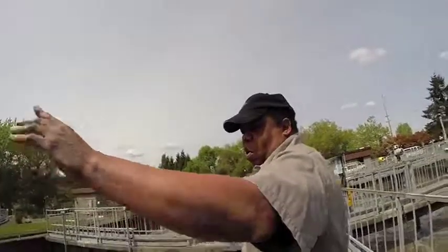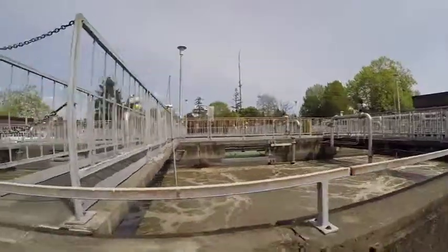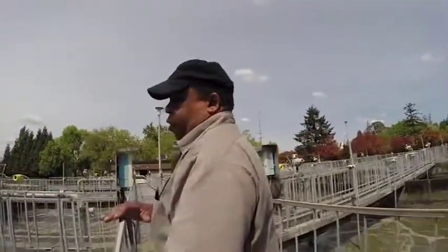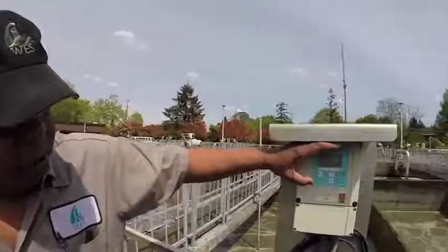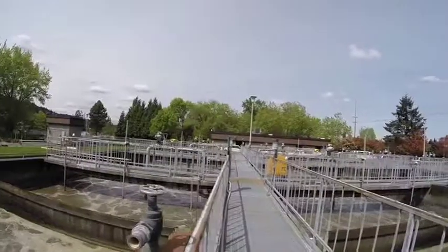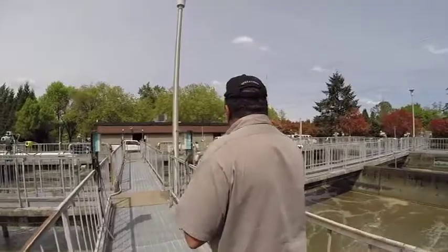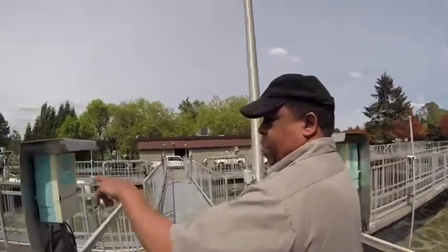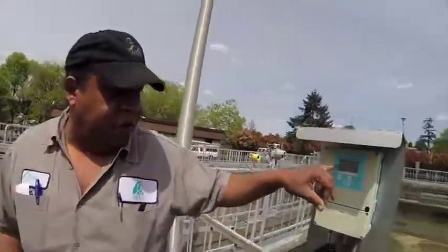Water's coming, let's see, how does that work? Water's coming over the top of the wall, being pushed down, comes underneath this wall, and back over, and from here on out, just straight on through. This section here is 1.58 on the air, and this one is 1.4. So as you do this, you want most of your air up front. And as it goes through, you want it to drop off. In the aerobic zone. Yeah, and anaerobic, aerobic. And see, it's dropped down a little bit. 1.3. This one's about the same.